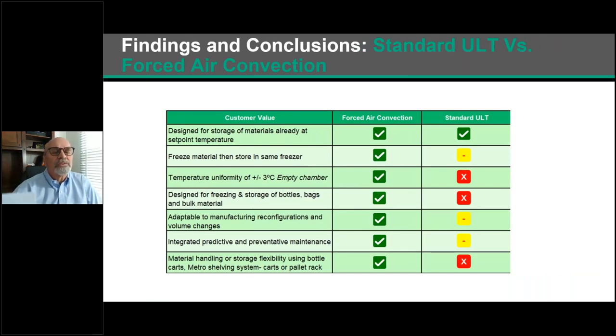The chart here shows summaries of key features of freezing and storing materials in forced air units versus standard ULTs. The green check marks indicate the best solution. Yellow means it could meet the requirements, but it's not ideal. And red means it's really not capable of meeting that requirement. Notice temperature uniformity of a standard ULT when it's trying to remove heat from material. It very likely falls outside of the acceptable ranges for some time. Unless you're freezing a very small amount of material, you will not have the cooling capacity to freeze and at the same time maintain the storage temperature in the freezer. The forced air unit includes that refrigeration capacity to freeze material while maintaining the temperature uniformity within the chamber.